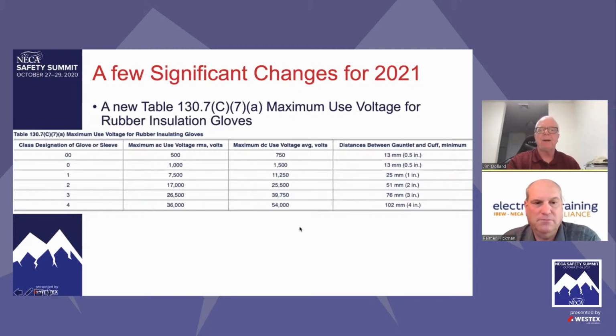Absolutely. And keep in mind, in the 2018 edition of the standard, we revised the table note, which is enforceable, to table 130.7C7. And it reads, new insulating equipment is not permitted to be placed into service unless it has been electrically tested within the previous 12 months. And that didn't change. But this new sentence now clarifies that insulating equipment that has been issued for service is not new and is required to be retested in accordance with the intervals in this table. So that means 6 months.